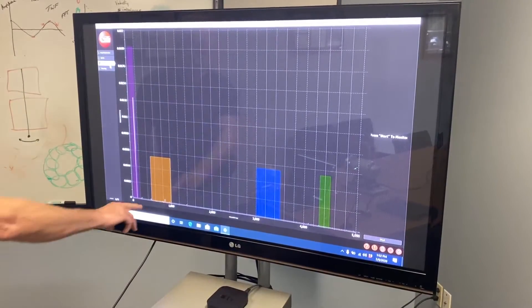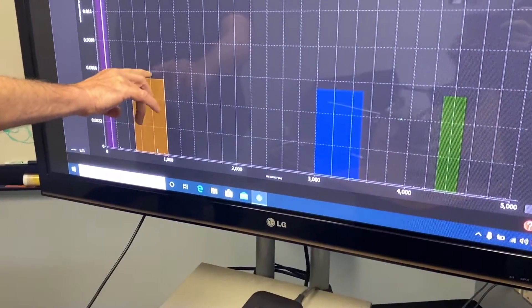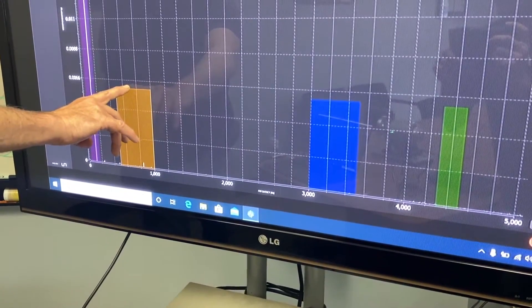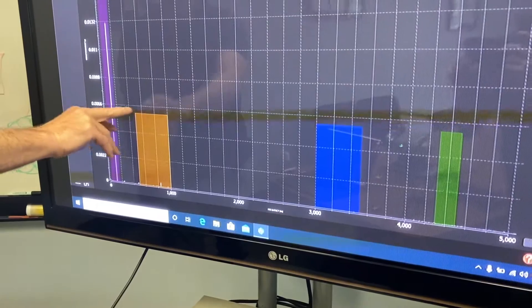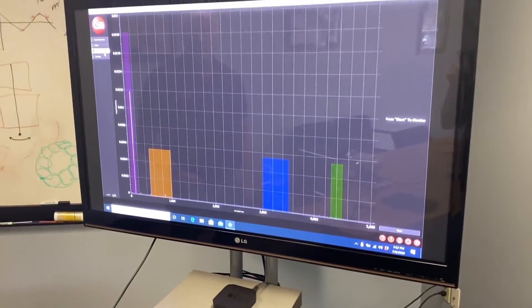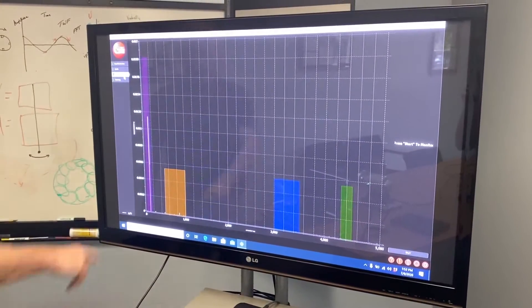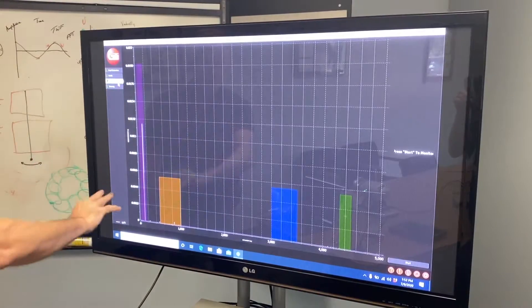This is our bearing frequency area, you can see there's a few little peaks there but if those bearings were to degrade and pass that threshold here I would know I have a bad bearing scenario coming up. And that data five seconds before and five seconds after would also go up to the web app. Now you can see I've got my one times running speed is now falling within the threshold that I've banded around.